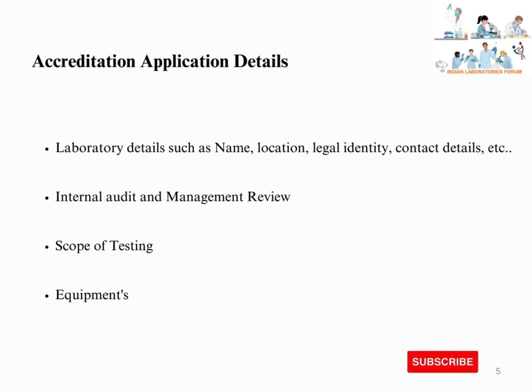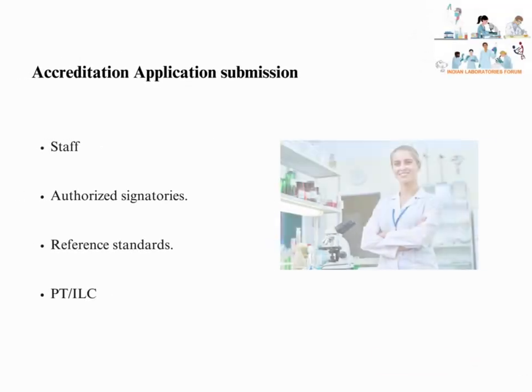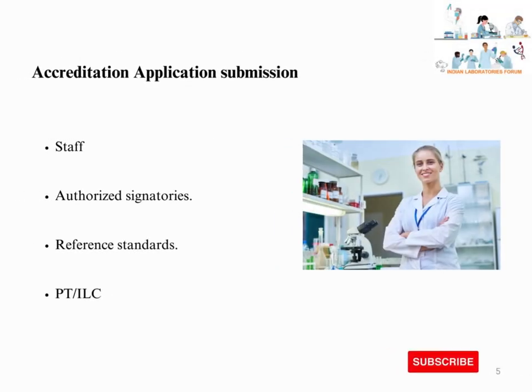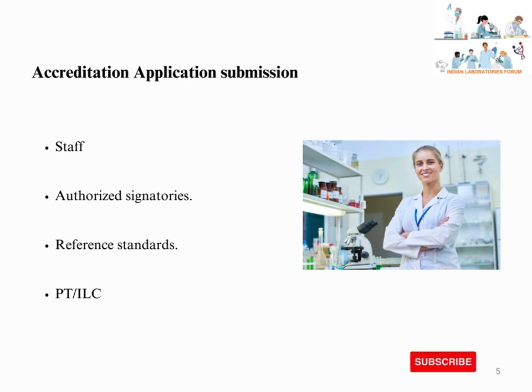Equipment details such as name of equipment, make, model, serial number, calibration date, calibration due date, and calibration done by details should also be provided. The laboratory should also provide details of staff — their names, designations, qualifications, and experiences — as well as details of authorized signatories for those authorized to sign off reports. Details of reference standards, such as name of standard, make, expiry date, and traceability details relevant to the scope of accreditation, are also required.